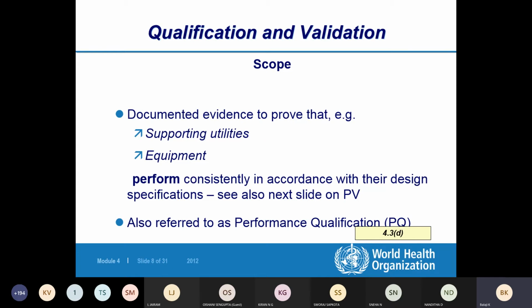That's it. Now you have to challenge with the load. What is the load inside the chamber? It is the Petri plates you'll be keeping, or any test tubes with the solution, or any other testing utensils like glassware sometimes. Whatever you are testing will be kept inside the chamber. Let's take an example of an autoclave. Whatever you are going to sterilize will be kept inside the autoclave. That is your load.